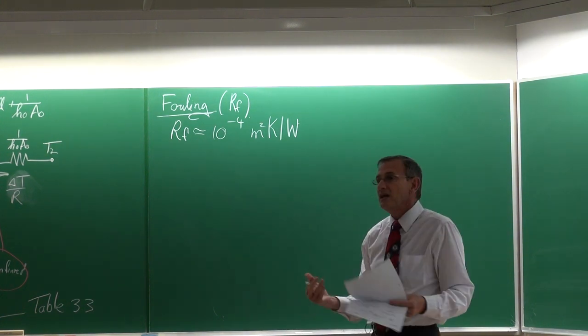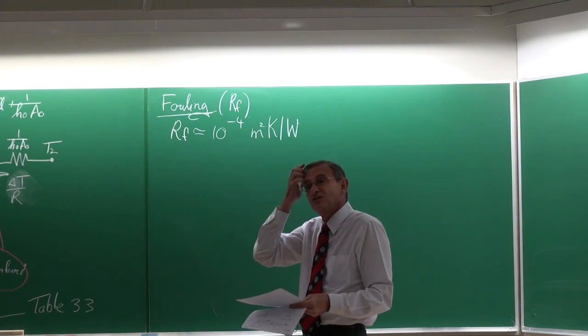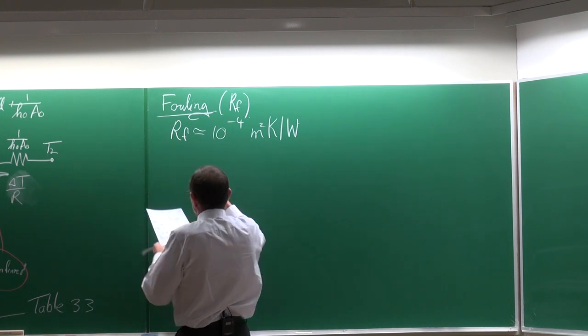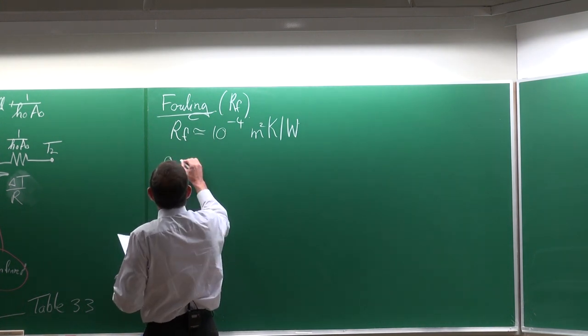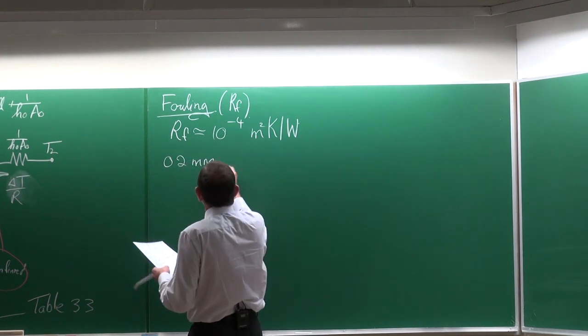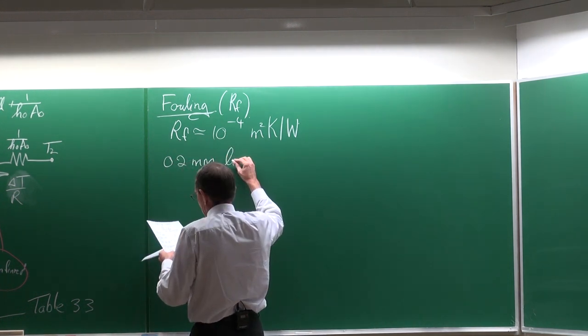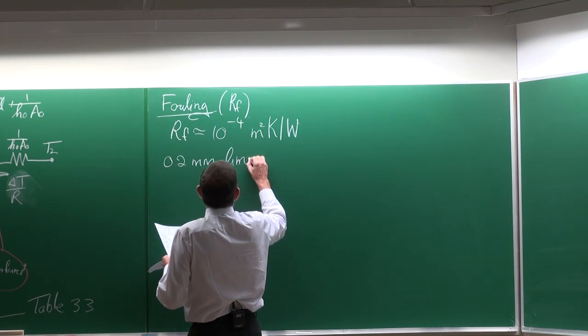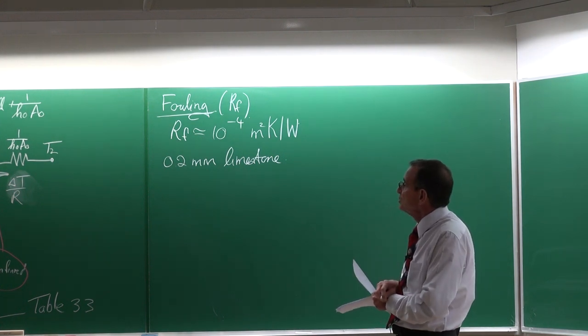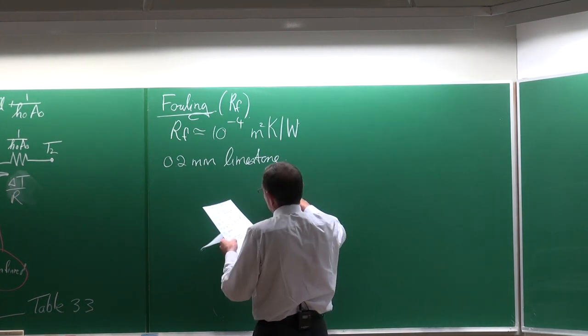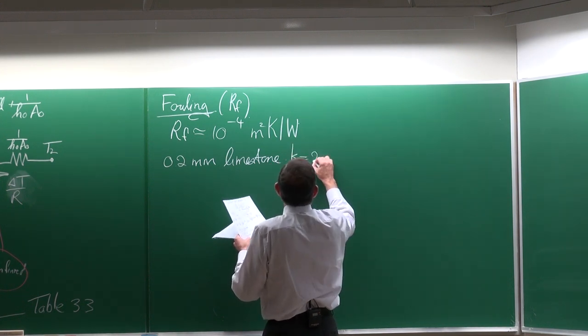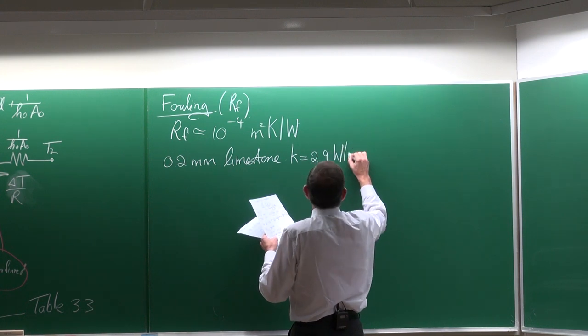These values can be difficult to understand in isolation, but if you do some calculations you can show that a typical scaling thickness of 0.2 millimeters of limestone — with a K value of 2.9 watts per meter Kelvin — would give you the same fouling resistance effect.